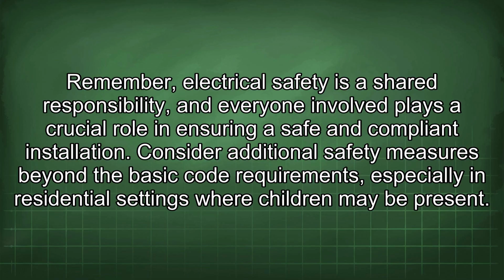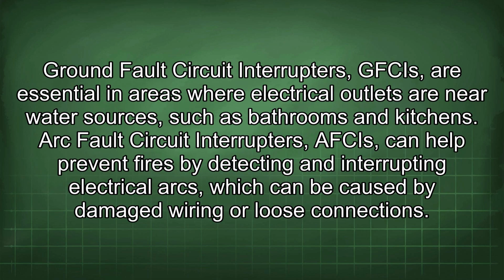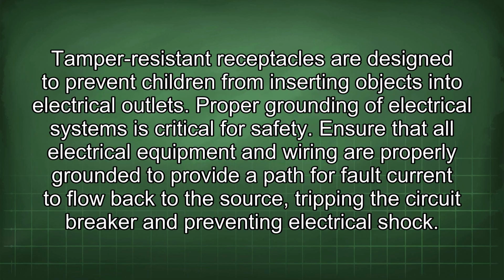safe and compliant installation. Consider additional safety measures beyond the basic code requirements, especially in residential settings where children may be present. Ground fault circuit interrupters, GFCIs, are essential in areas where electrical outlets are near water sources, such as bathrooms and kitchens. Arc fault circuit interrupters, AFCIs, can help prevent fires by detecting and interrupting electrical arcs, which can be caused by damaged wiring or loose connections. Tamper-resistant receptacles are designed to prevent children from inserting objects into electrical outlets.